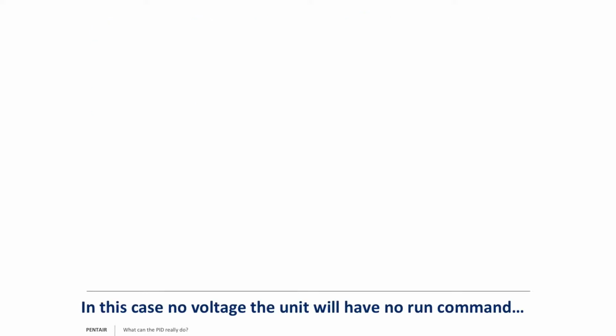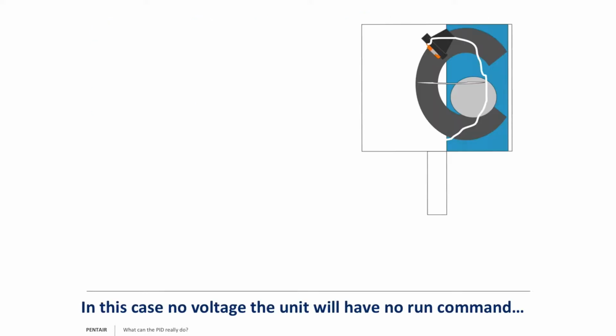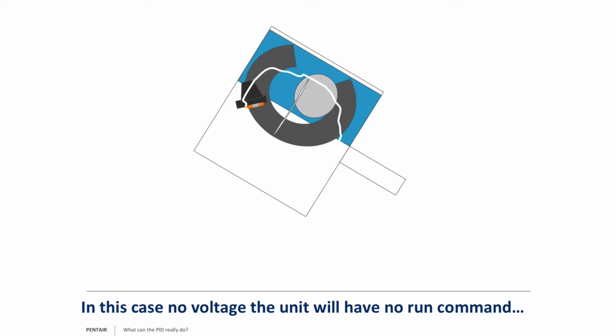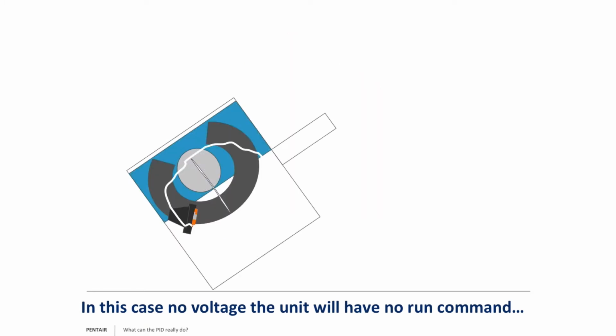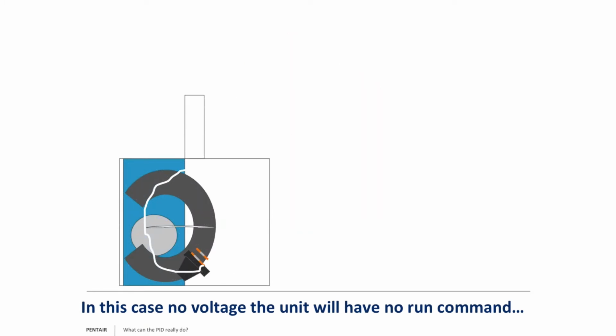So again, let's get back to our float switch description. So here, when my water cistern is full, the points have closed, and it's passing current down to the drive into input 1 using the 24 volt power supply on board. As we pump water down, the float will start to tip with the water level. When it gets to the down position, as you see here, the point's fully open, stopping the current flow.